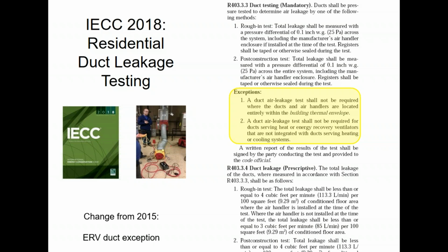That's a pretty low number. That's a really, really tight duct system, so you're going to have to be pretty aggressive on the duct sealing effort. Obviously, at TEC, we support AeroSeal. It is reasonably easy to get to these numbers with an AeroSeal type system, but I know everybody doesn't have that equipment. But if you are an AeroSeal dealer, this should be a great opportunity for you, and you may want to partner up with other contractors in the area who are having trouble manually sealing it down to the required leakage rates. So once again, all ductwork must be sealed.